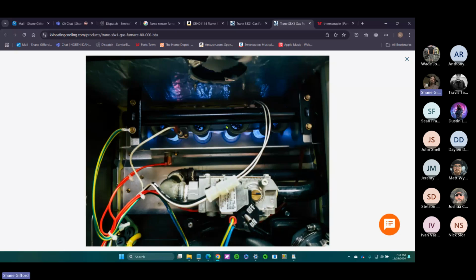I have. Dude, it went kaboom and blew the lid back, nearly broke the damn thing. That was because my cavity where I'm going to ignite was full of gas. But that's another reason why we have this inducer motor: it is drawing that gas through the burner and out the smokestack. That's why we have these safeties and why you never want to bypass any of these. You don't want to bypass a pressure switch on a gas pack because you might just create a bomb. You don't want to do that.